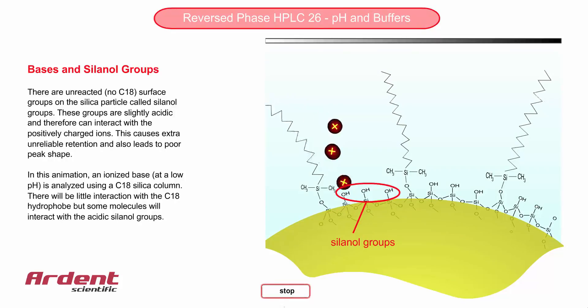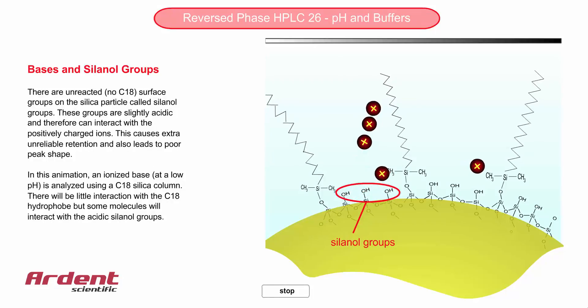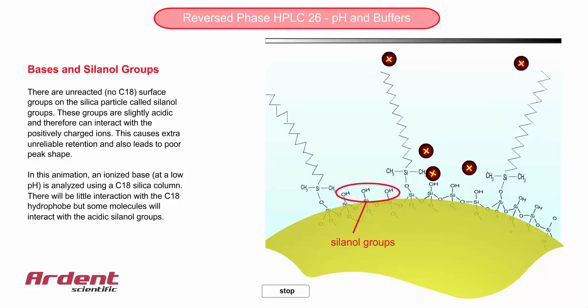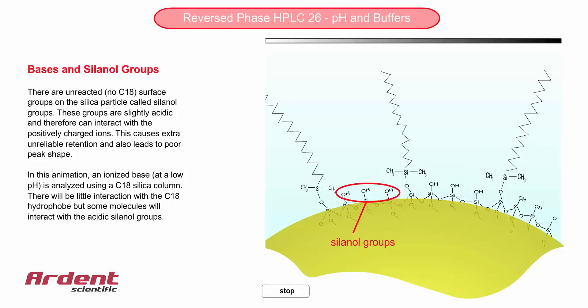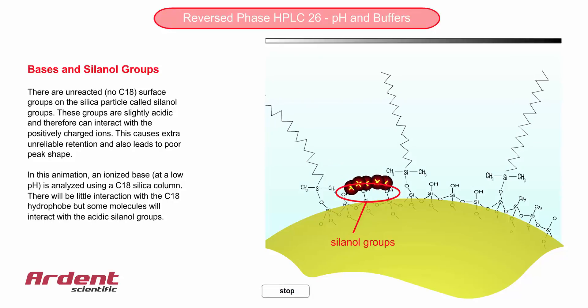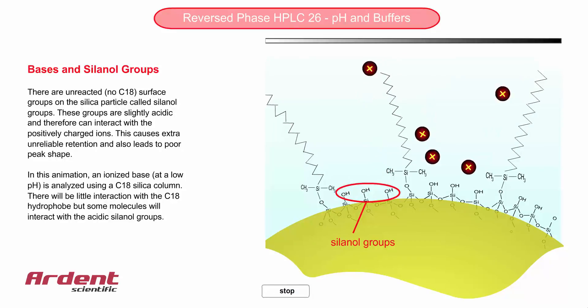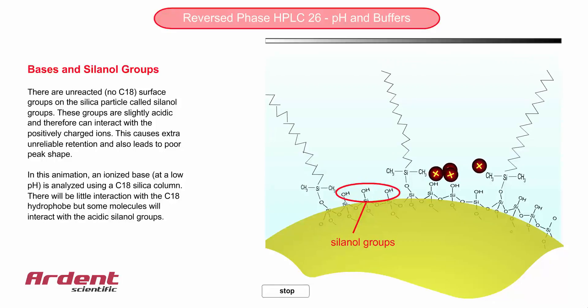This interaction with the silanols can still occur for a non-ionized base, but there is a common way to minimize this, and that is to neutralize the silanol groups with a smaller hydrophobe, such as a C3 hydrophobe, which is small enough to get in close to the silanol groups to react. This whole process is known as endcapping the column.